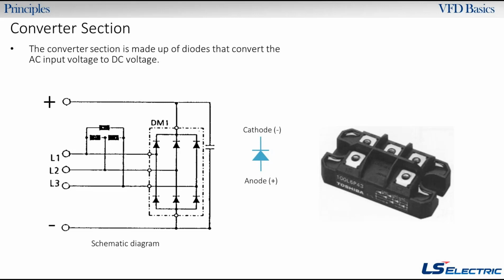So there's 2 pulses for each phase. So there's phase 1, which is L1, 2 diodes. L2 has 2 diodes, and then L3 has 2 diodes. One for the positive side, one for the negative side. So this is like your DC bus. That's what this capacitor is right here. So this would be a 6-pulse drive, okay? So there's a positive and negative pulse for each phase.